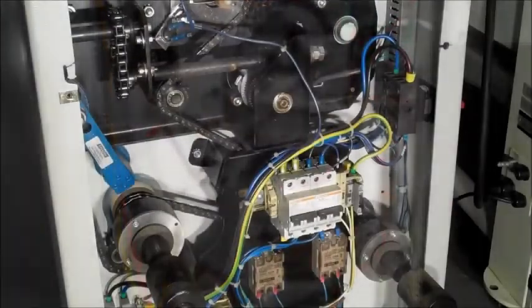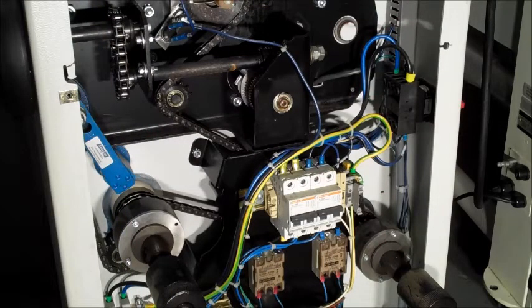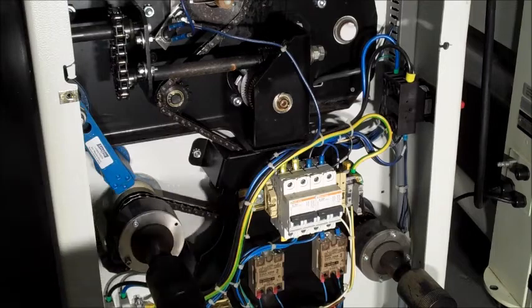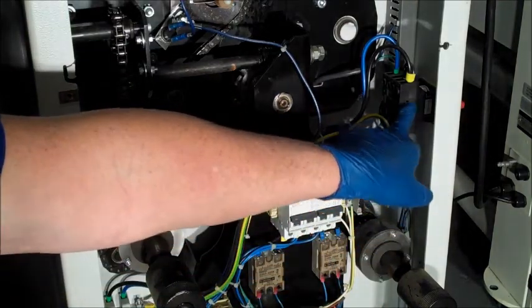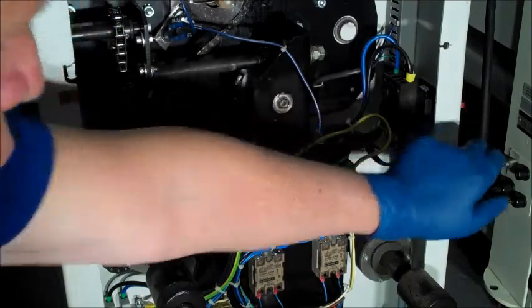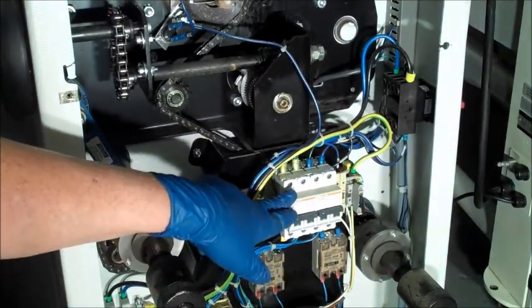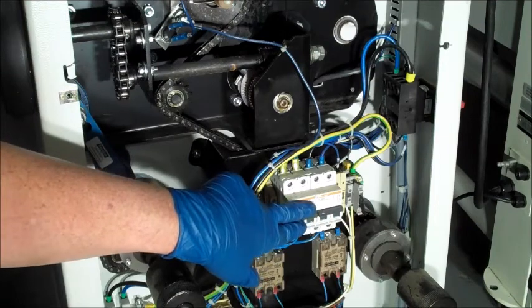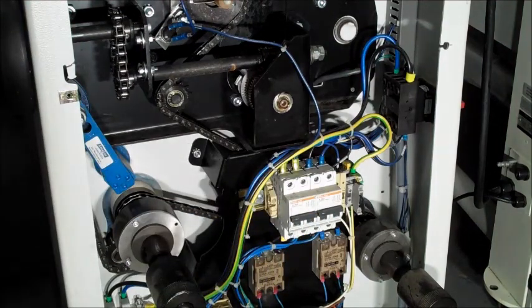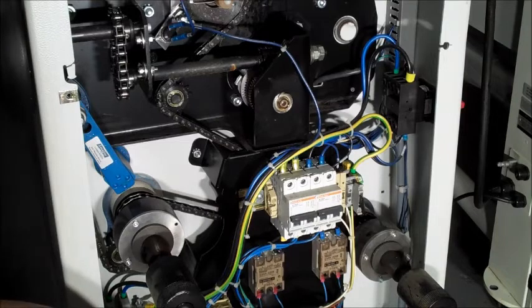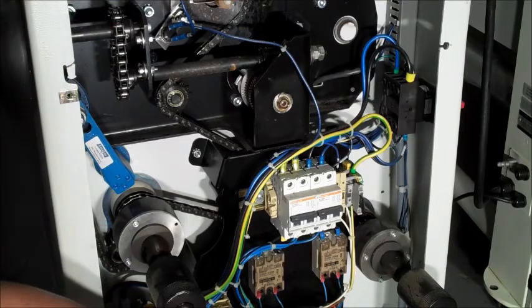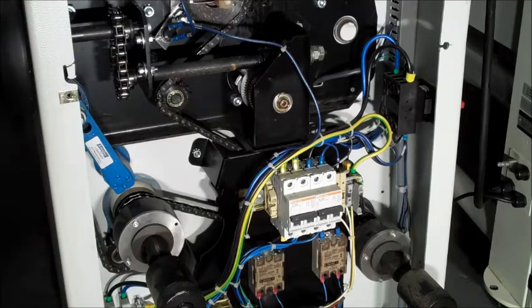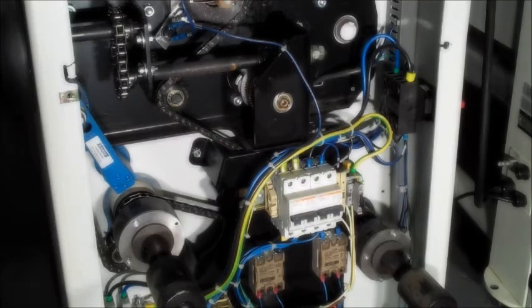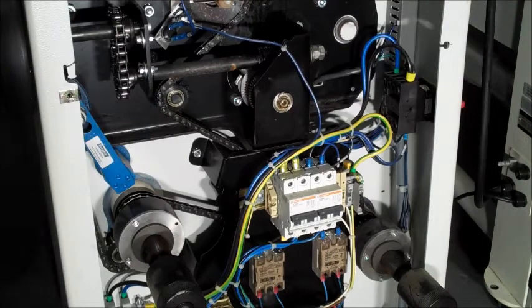Now we're looking at the inside of the Seal 62 Pro, and as we said, a lot of things in common here. You've got your main service coming in through your power switch, and then it's going to be distributed through the machine with circuit breakers. And then instead of a power supply on this one, Seal uses a transformer, and you can see all these different color wires are different voltages that come off of that transformer, and you can troubleshoot that if you're missing one of those voltages.